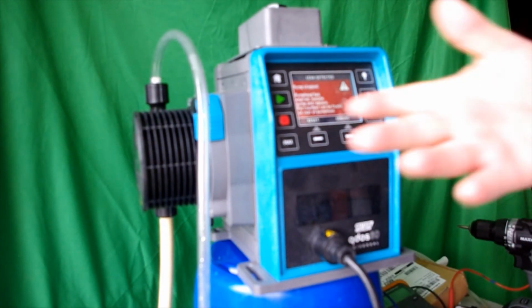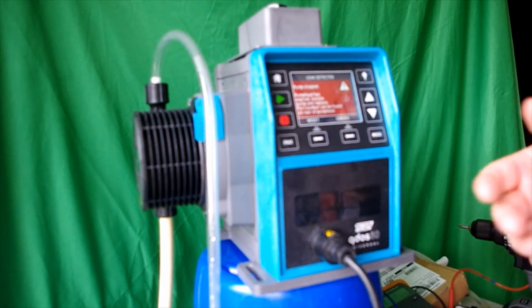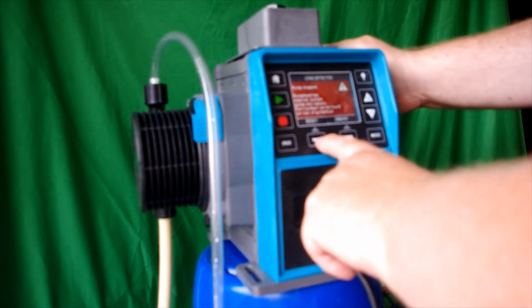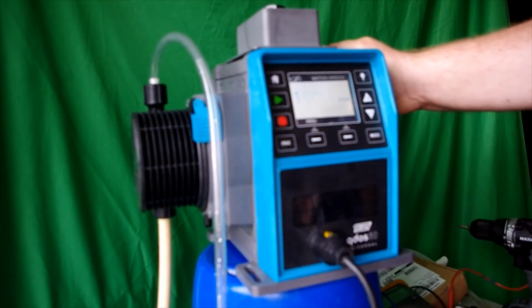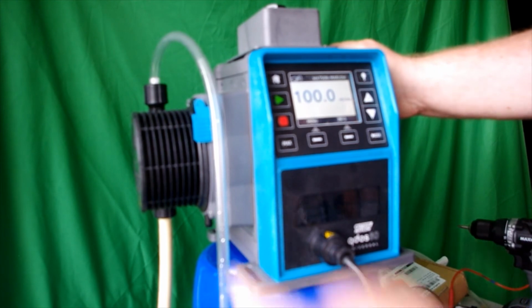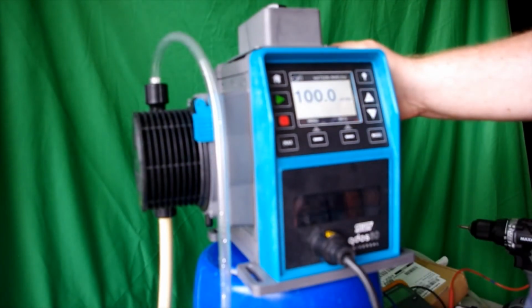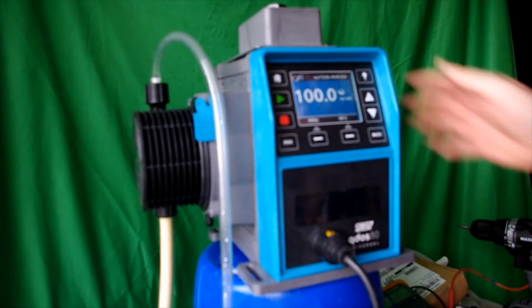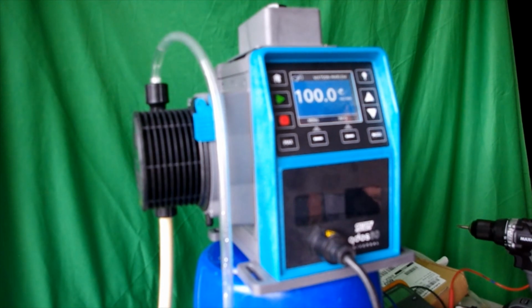And as you can hear, the alarm is now stopped because the pump head's now on and this doesn't have a leak. So I'm going to reset my pump head now. And your pump is ready to go. Your new hydraulic connectors are all hooked up to your brand new pump head. Press start and you're pumping again. Hope this was informative.